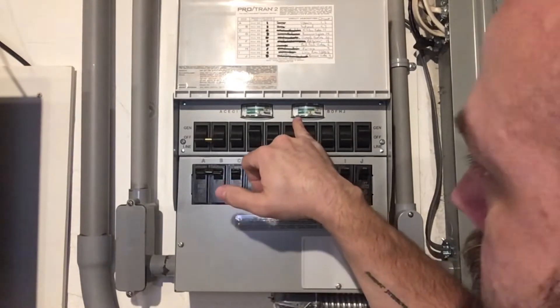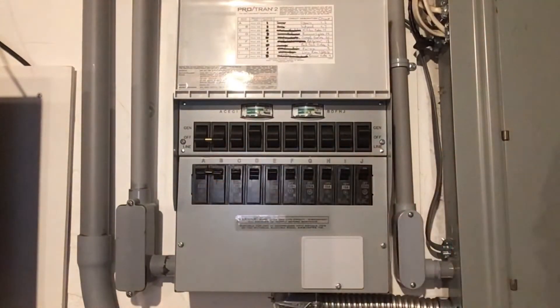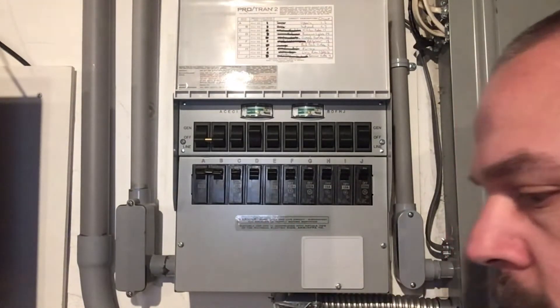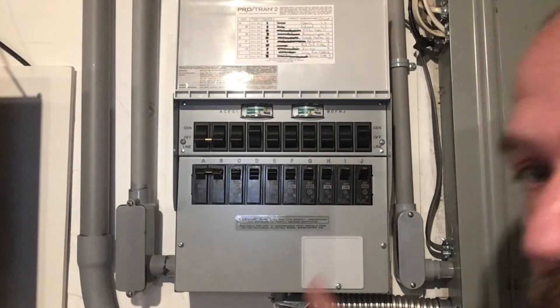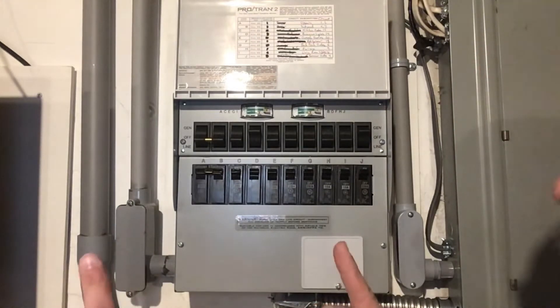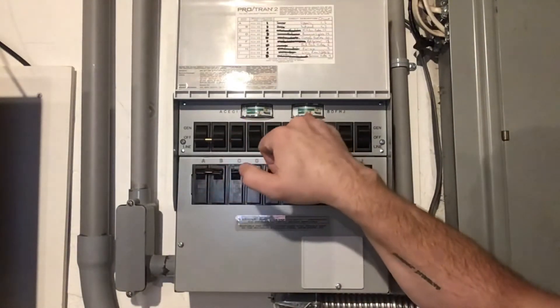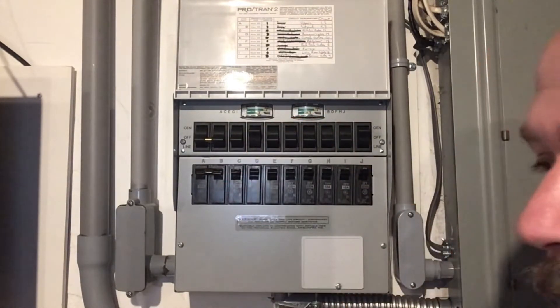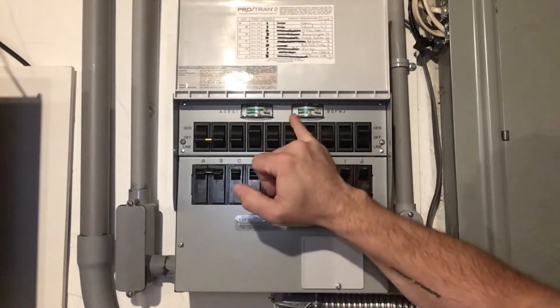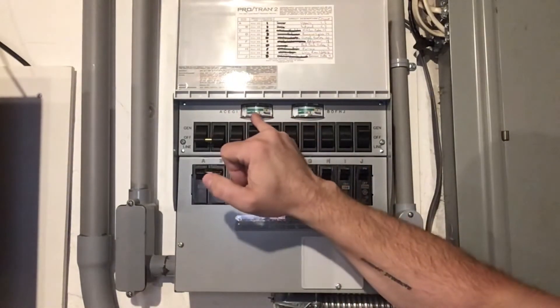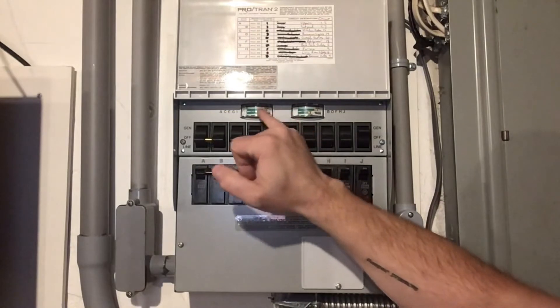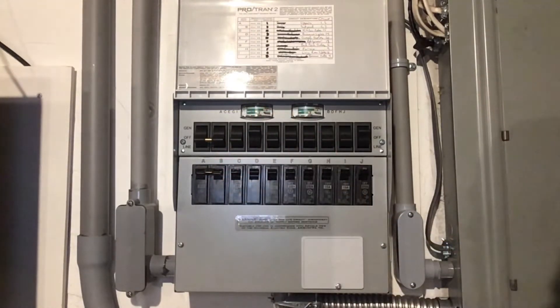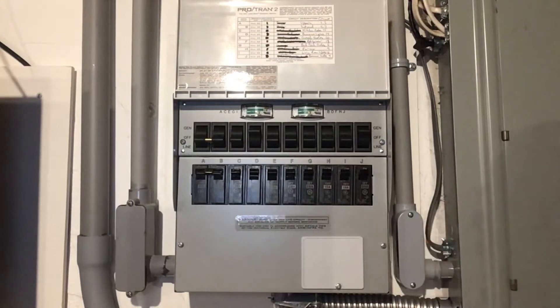Up here, you can see we have a meter. So this is a 240 volt generator powering this panel with 240 volts. 240 volts isn't actually 240 volts. It's two separate 120 volt leads. So this is one half of the generator. This is the other half of the generator. And this is true for all 240 volt generators and for that matter, the power coming into your house. You want to make sure that neither one of these gets above the capacity of the generator. If one of them gets really high and the other gets really low, that can damage the generator. So you want to make sure that that electricity is balanced between the two halves.